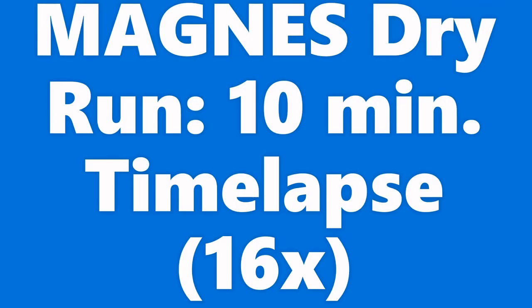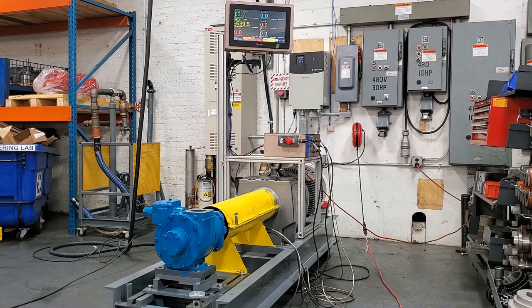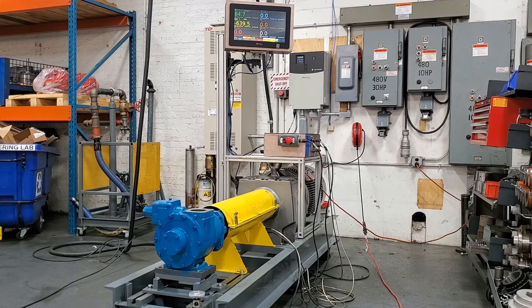To demonstrate the pump's dry run performance, a MAGNES pump was run dry at max speed for 10 minutes. This is a time-lapse video that shows the dry run at 16 times normal speed. The surface temperature near the magnetic coupling was recorded and displayed on the screen above. It can be seen that the surface temperature only rises about 7 degrees Fahrenheit. This can be attributed to friction with the vanes, shaft, and bushings.